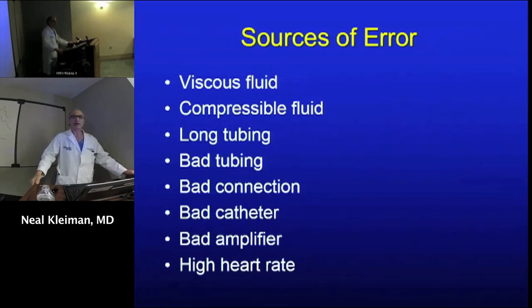What else is a bad catheter? A catheter that's compliant—same as compliant tubing. You want to stretch the transducer, you don't want to stretch the catheter. For Swan-Ganz catheters, they have narrow lumens and they're compliant, particularly if they've been in the body for a while and they're warmed up. So this is a problem you have to be aware of.